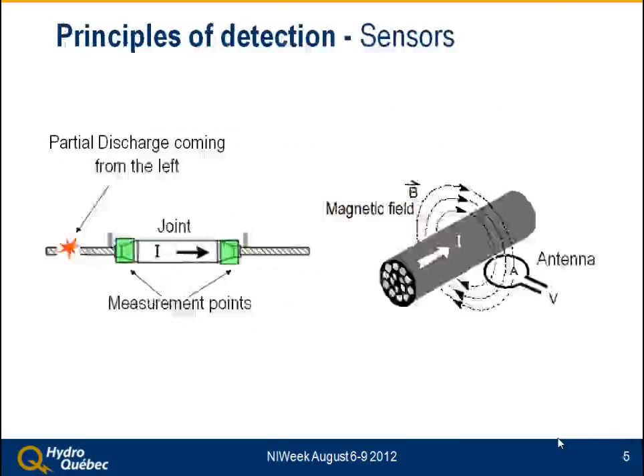So to continue, the principle of detection: when you have a partial discharge - as you can see, there's one just on the left of the joint - there is a current generated, because a signal is created, traveling on each side of the breakdown.